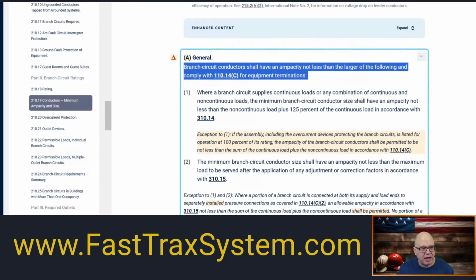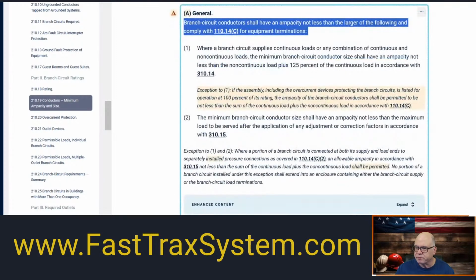Again, it doesn't apply to non-metallic sheath cable. That's in 334.80. You have to read it. And that is never going to exceed the 60-degree column. Even if you use a 90 for adjustment and corrective purposes, you're never going to exceed the 60. That's not the same when you're dealing with 110.14(C) for regular wire, like THHN, XHHW, things like that. Okay. Anyway, so here's where we're at.